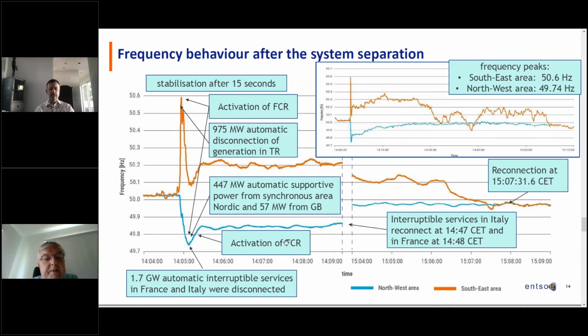We also had activation of frequency containment reserve. And there was also, relatively new, supportive action from the Nordic area and GB over the DC connectors. We've installed frequency support on the DC cables between synchronous areas for a few years now, and this indeed helped a lot - 447 megawatts from the north, 57 megawatts from GB. This can of course also run in the other direction: if the Nordic area has a need, Continental Europe can supply supportive power, and same towards GB.